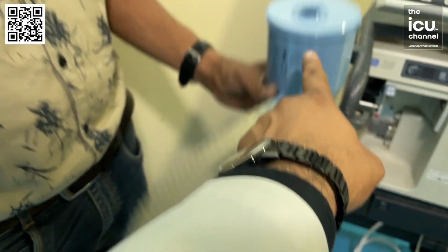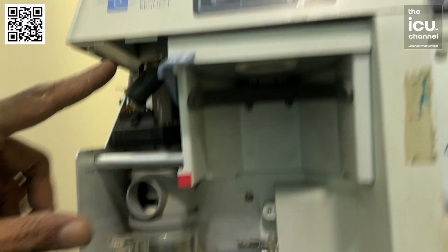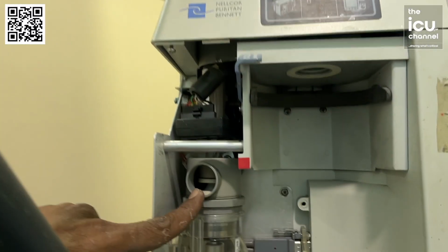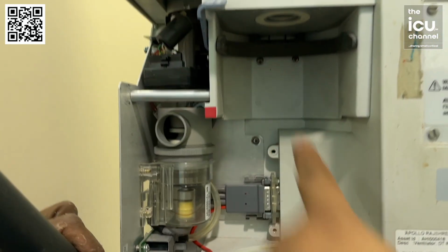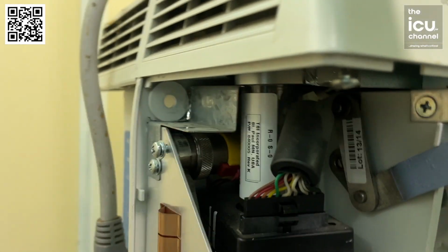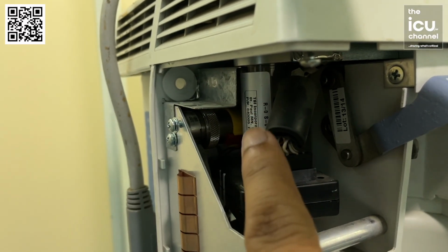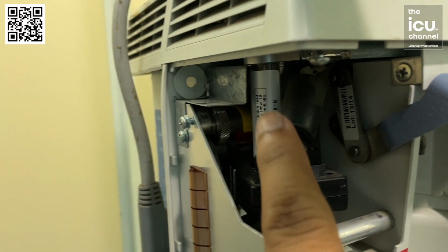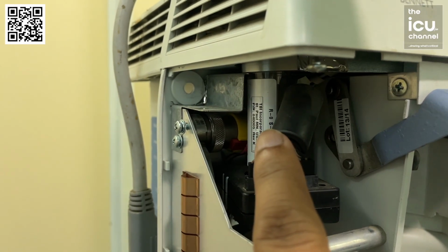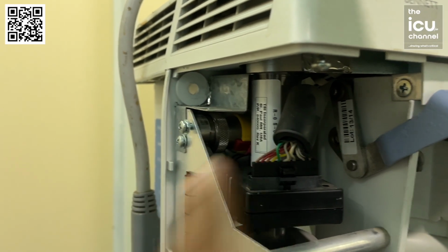First it comes to the expiratory filter, and this filter filters out all the impurities and the bacteria through it, and from here it goes to the expiratory valve going via the flow sensor. You can see that this is the flow sensor, and it is checking how much tidal volume is coming from the patient, meaning the expiratory tidal volume, which is being sensed by this flow sensor, how much tidal volume is detected at the expiratory limb.